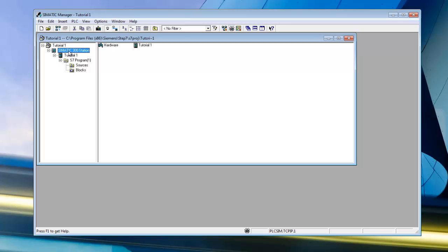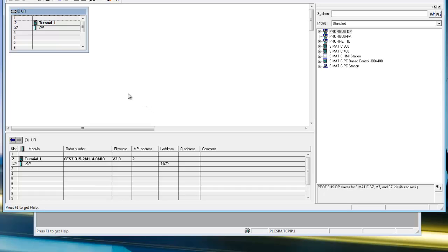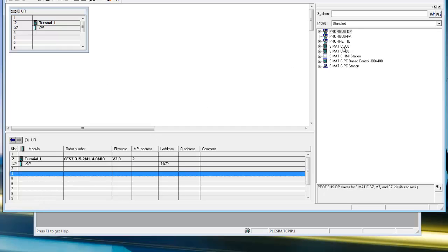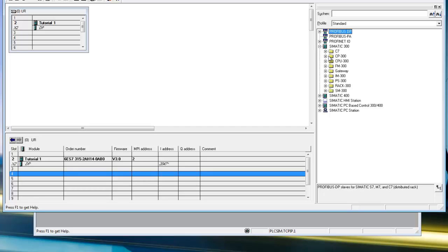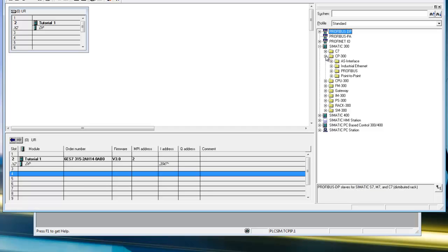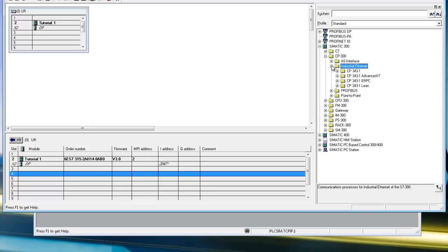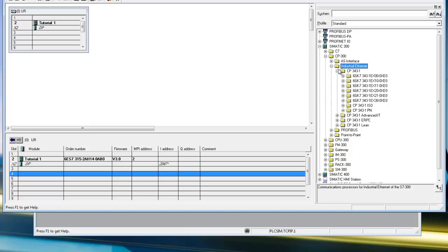We're going to go back up to our station and configure our hardware. We're going to add a SIMATIC NET, which is an industrial Ethernet module, and it only goes into slot four. We'll go to Simatic 300 since we're building against a 300 processor, then go down to CP300 and Industrial Ethernet, and down to the 343 module.